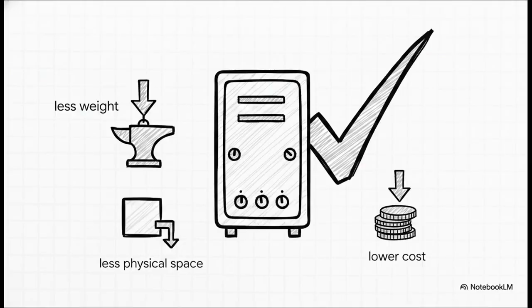So let's quickly tally up the massive advantages of the multi-drive topology. By centralizing that filtration and sharing a common supply, you need far fewer breaker feeders in your switchgear. That translates directly into physical space saved in those super tight electrical rooms, a really significant reduction in overall rig weight, and a much lower total switchgear cost. It essentially turns the whole complex headache of harmonics into a predictable, streamlined engineering solution. You design it centrally, you build it once, and you can absolutely trust it.